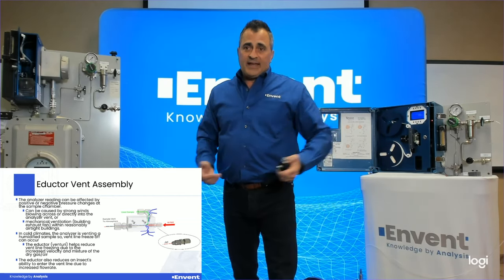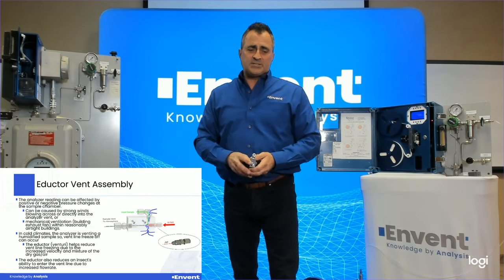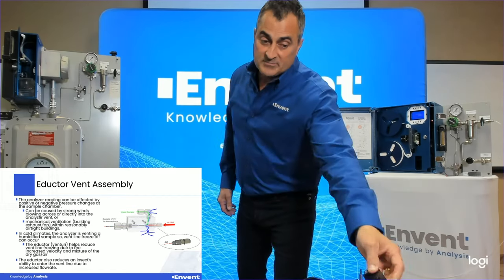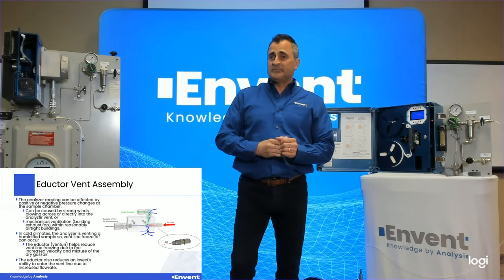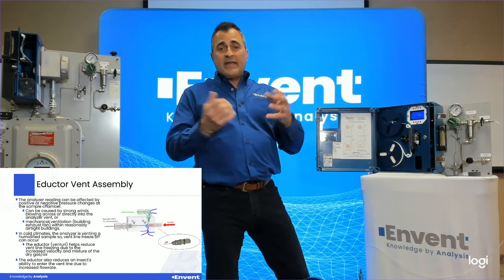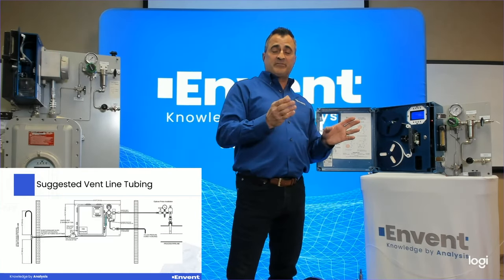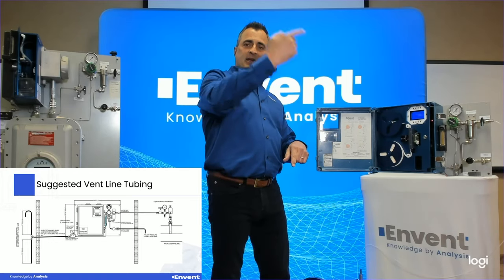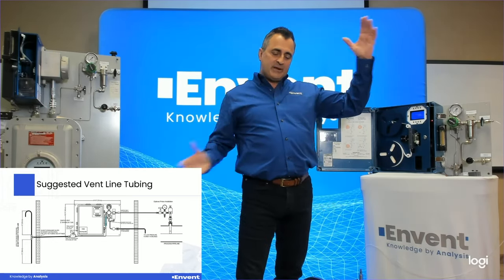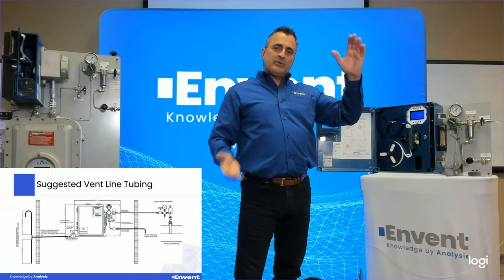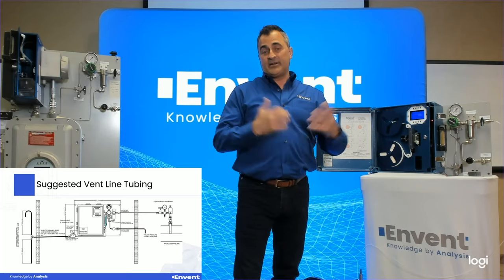Another advantage is we increase the flow out the vent so much that insects have a hard time getting in and building nests, which has occurred in the past. Downstream of the eductor — we call it a candy cane — it eliminates pressure going straight onto the vent header end. That was designed by Envent Engineering.